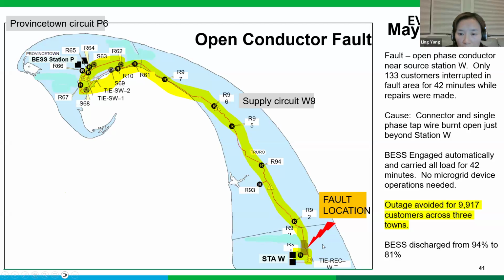So back in May last year, a fault happened somewhere near the source station. Within 1 minute, the battery was able to carry the load from almost here towards the source station. The only customers impacted are somewhere after the recloser opened. So we successfully picked up more than 9,900 customers, and only a small number of customers were impacted during the fault.